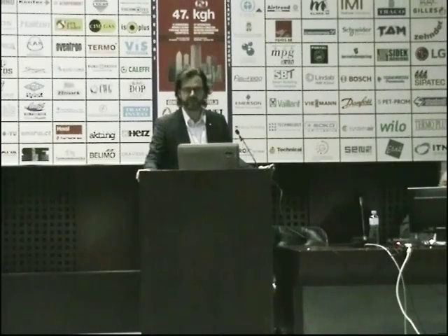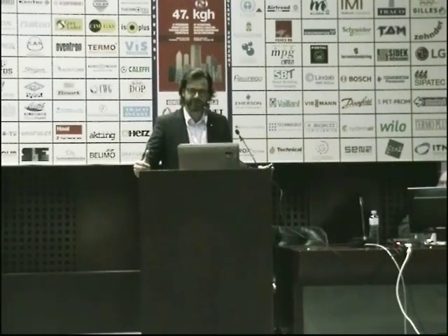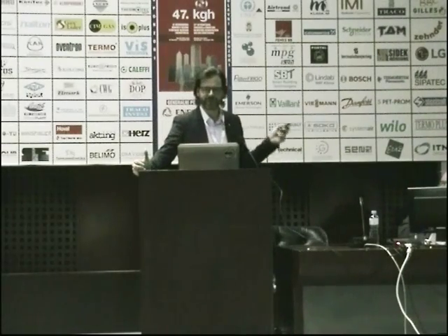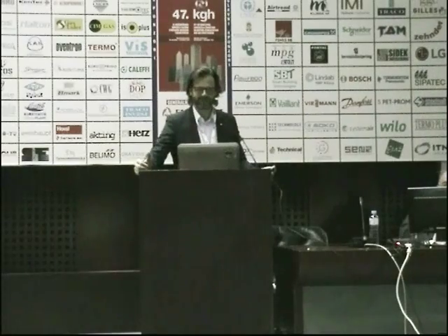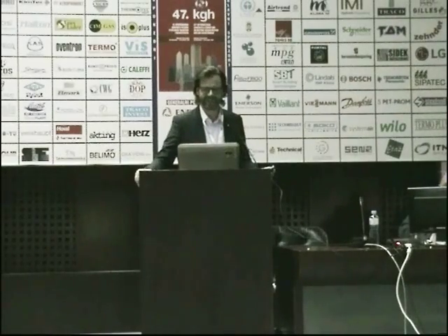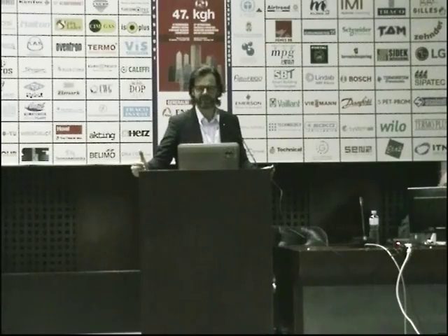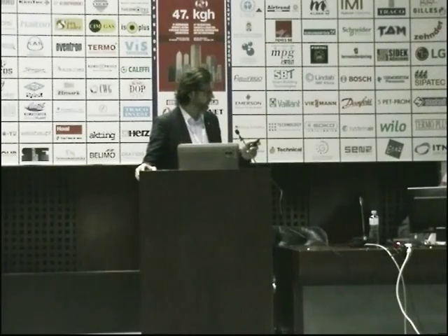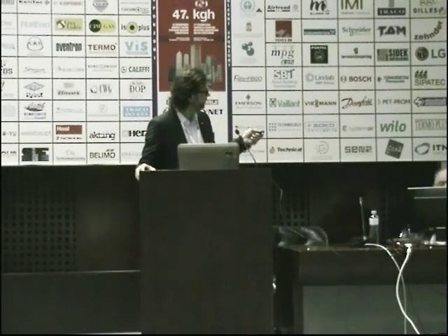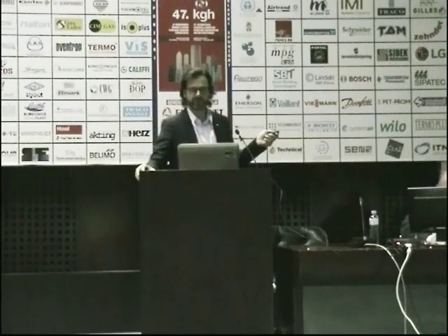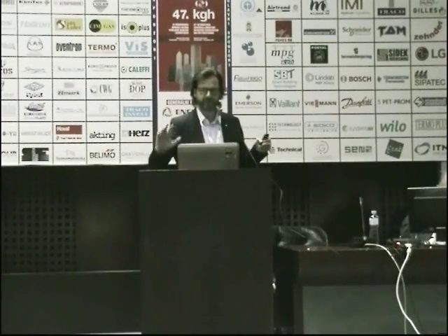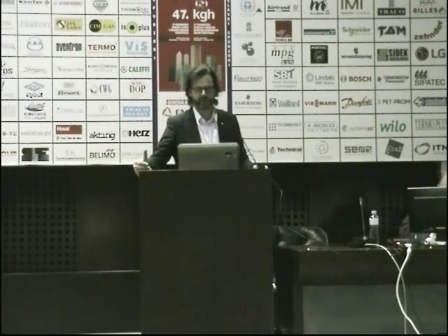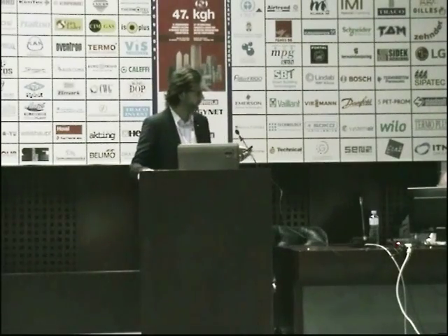Which is funny, because the Johannesburg system should not be as good as the Cape Town system, because we have a second circle inside and we do not condense the CO2 directly. I think it's also a matter of running the system, because the market manager changed in a while, and then how they close doors, how they put goods in cabinets and whatever, so it has a great influence on it.